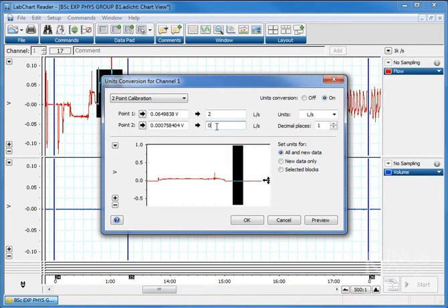liters per second. You can see that the actual calibration of the system was probably 0 volts being 0, and it's difficult to interpret perhaps what the voltage was for various liters per second, and it does depend on the device you're using. So if you do have a recording that maybe doesn't have the recorded calibration at the beginning, you could perhaps use these as ballpark figures, but of course without the calibration you can't be absolutely sure what the numbers are.